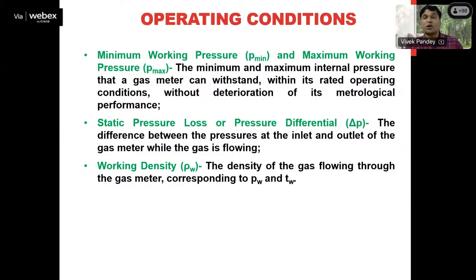Then there is a static pressure loss or differential pressure. This is also a very important parameter in gas meter functioning. Why? Because if there is a pressure loss more than the pressure loss specified by the manufacturer for a certain gas meter, there are definitely chances of lesser accuracy, or the error observed will be more. Suppose a gas is passing through the gas meter, with a manometer connected on the inlet side and a manometer connected on the outlet side. What is the difference in pressure because of the gas meter? What is the drop in the pressure of the gas supplied through the gas meter? That drop should not go beyond a certain limit, because if it does, it means your measuring instrument is not working satisfactorily. Okay, there are chances of errors.